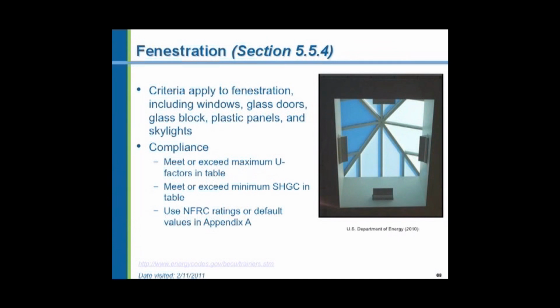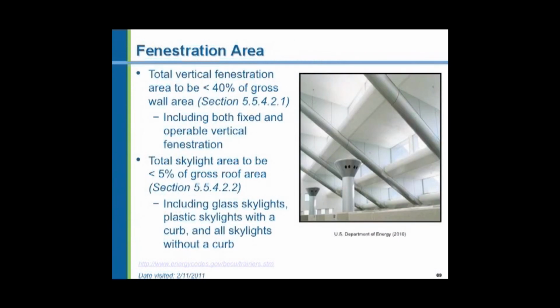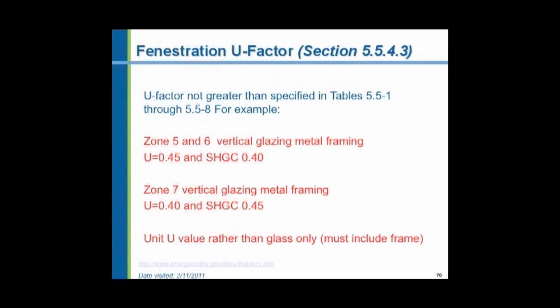Now, the residential code does not require compliance with solar heat gain coefficients. The commercial code does, however. So that you folks who are building both residential and commercial structures know there's a difference. You can get away without having to worry about solar heat gain for residential, but you must worry about it for commercial. And again, using the prescriptive option and complying with the code, we can use no more than 40% of the outside wall area as windows and no more than 5% of the roof area as skylights.